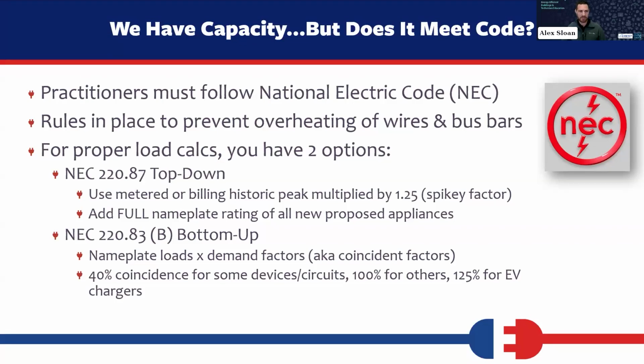The more typical one is the bottoms-up approach, where we go throughout the home and take the different nameplates of the main electric-using appliances in the house, figure out what their demand factors are, combined with a discount rate for certain appliances that aren't running all the time, because usually we're not using every single appliance all at once. Some do require 100%, what's called a coincidence factor, because they may be running for longer periods of time, such as an HVAC system. We put all those together, and eventually that's going to spit out a result to say whether or not we can continue utilizing the existing service.